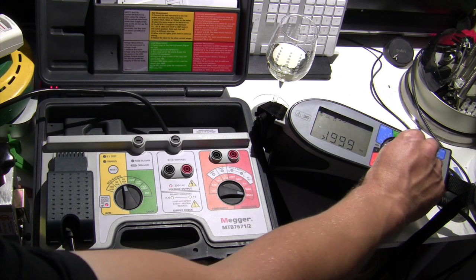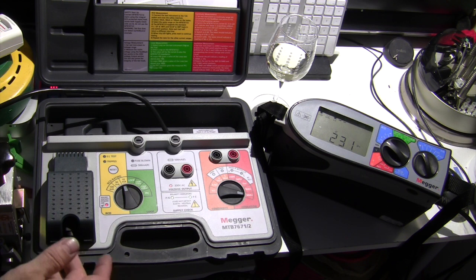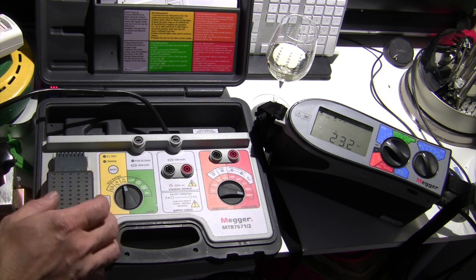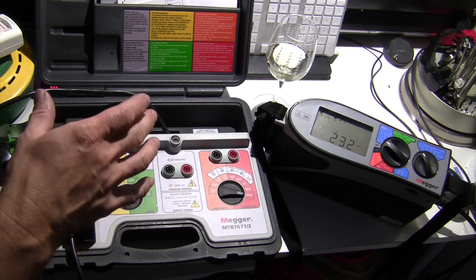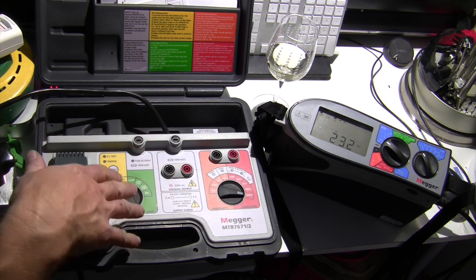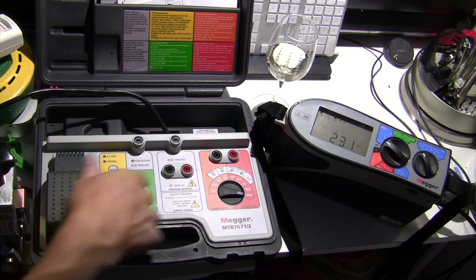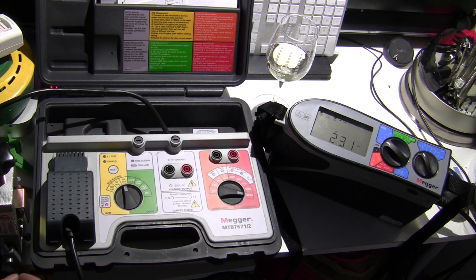Now we're going to switch to the 1 times test, or the rated current test. So we're going to send 10 milliamps of simulated earth fault to this device, and we're going to do that at 0 degrees on the waveform, and we should see a trip within a certain time period. Now those who are familiar with BS7671 will know that an RCD to BS61008 should react within 300 milliseconds at rated current, or at 40 milliseconds at 5 times rated current.